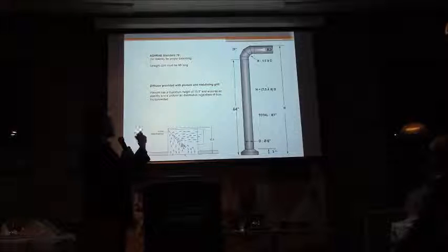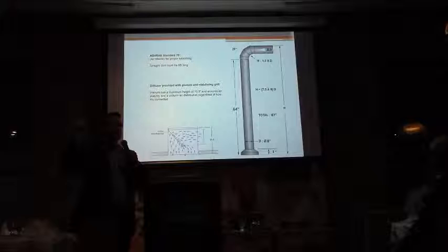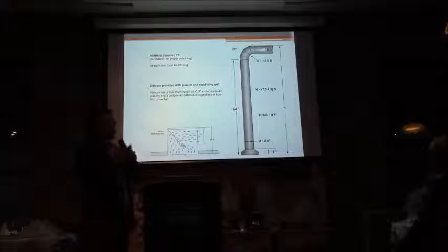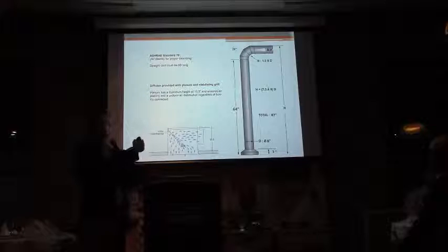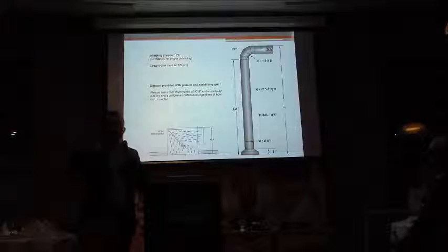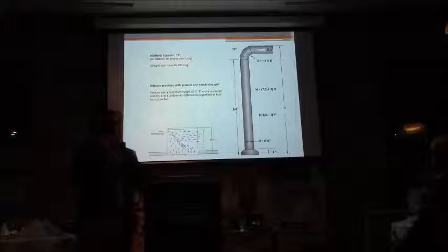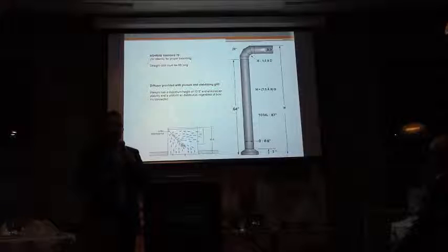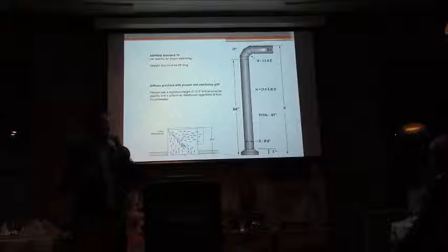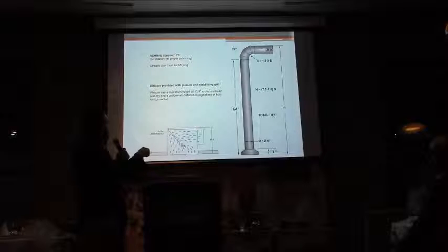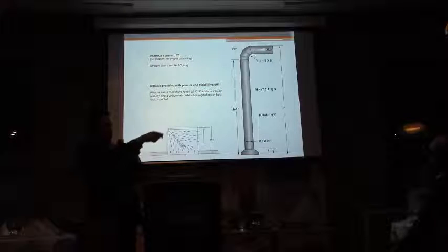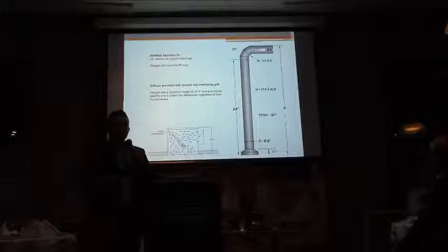While the other one, the high induction, is actually a European diffuser. So they don't test them with these same lab conditions. They don't believe in ASHRAE there, they have something else. So whenever they tell you it's 34 decibels, it's actually 34 decibels in the field. And the second thing is that they come with a plenum typically. I saw one in the entrance there. And if you see, they all have a plenum. If you go to Europe, every diffuser has a plenum.